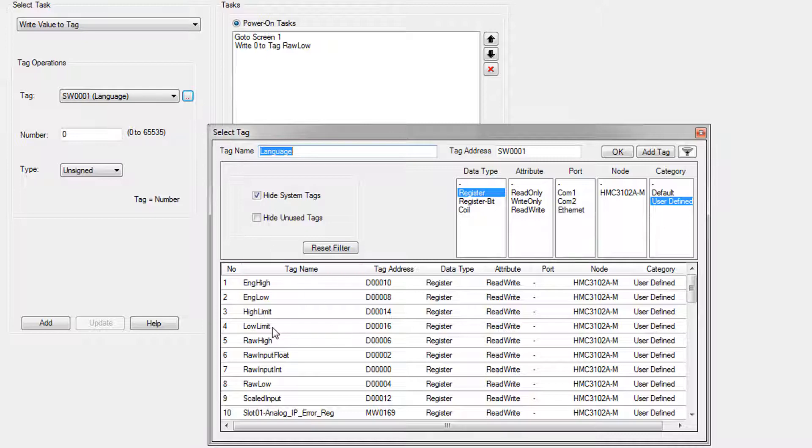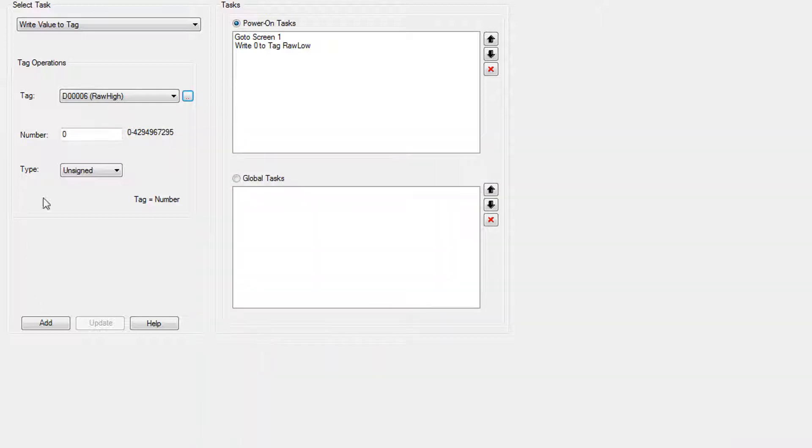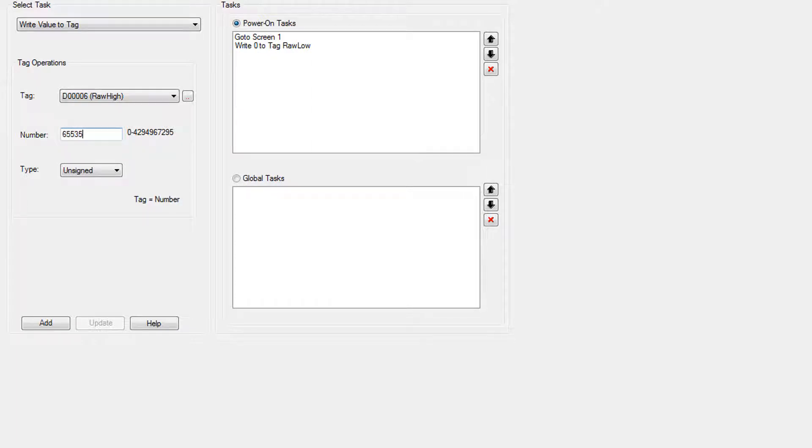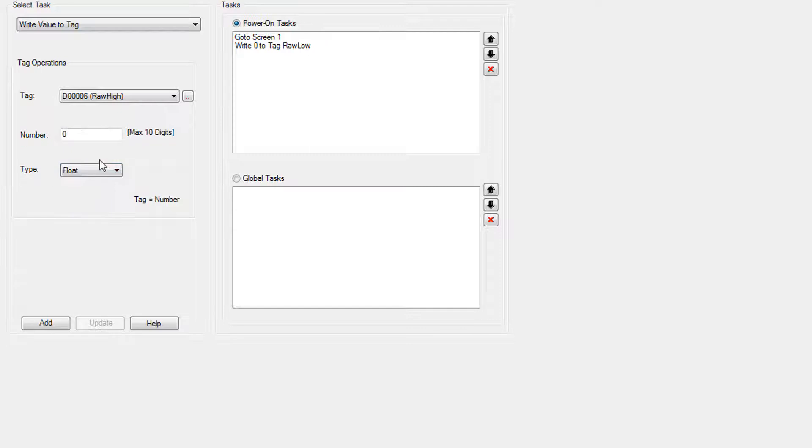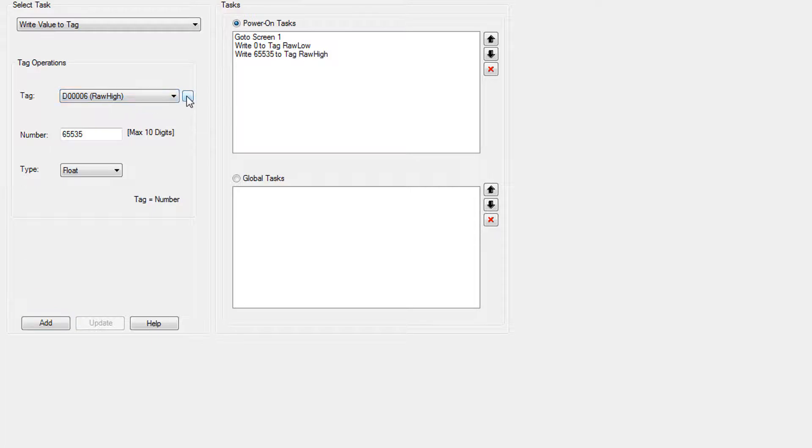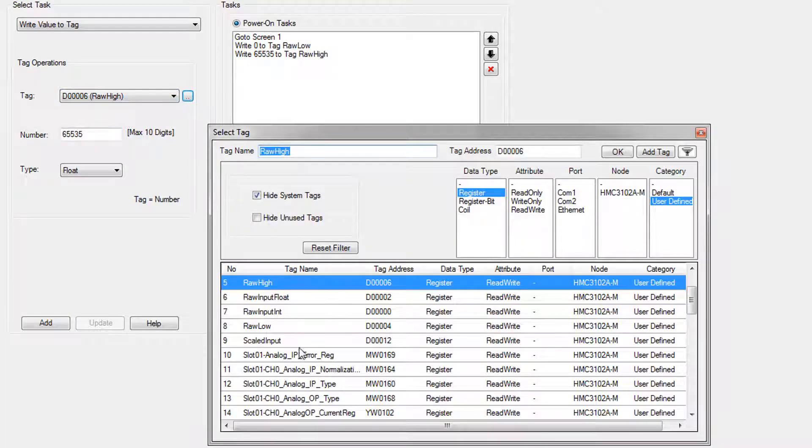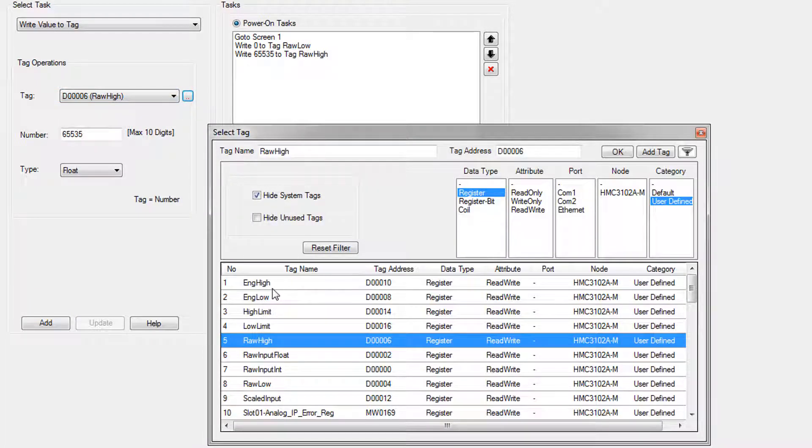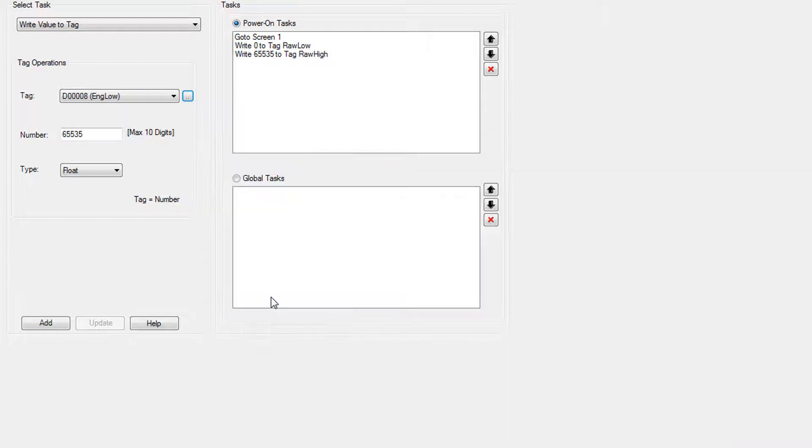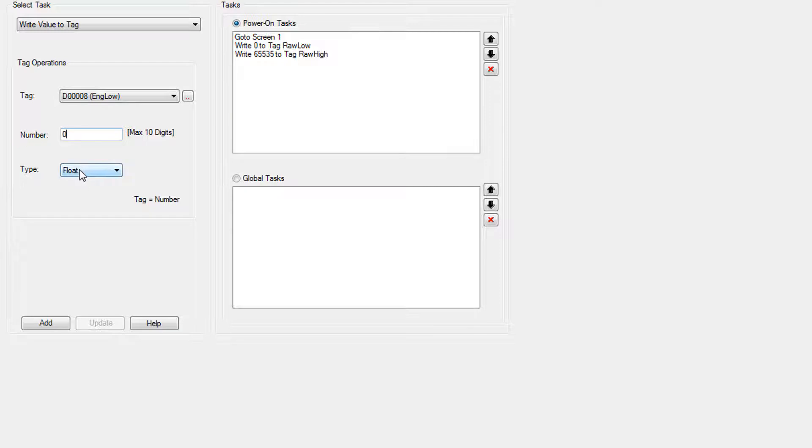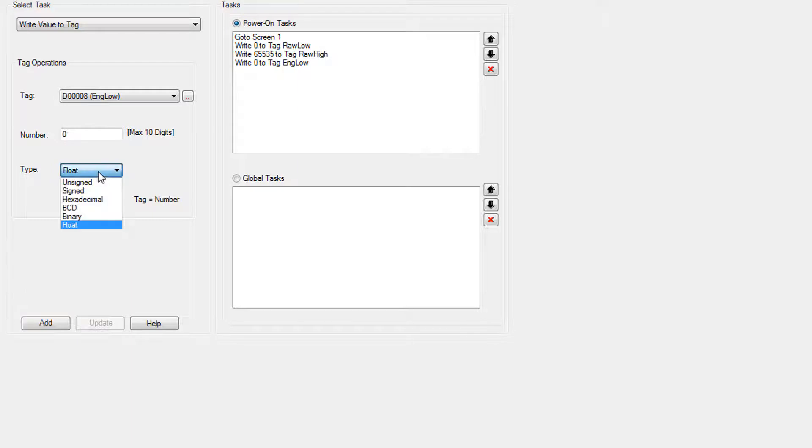So that was rawLow. Let's grab rawhigh. And we're going to write 65,535. And this is going to be a float again. Click add and let's change this number to engineering low. So the engineering low is zero. Leave it at float because all of these variables are four bytes long and floats are four bytes long. We want to make sure that we have the length of the tag correct that's getting written here.